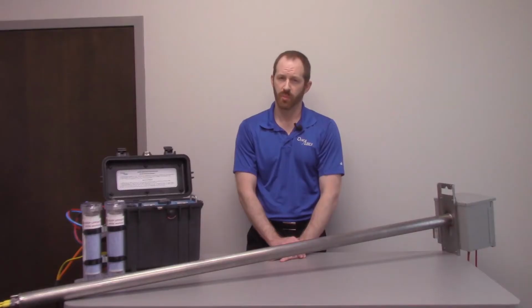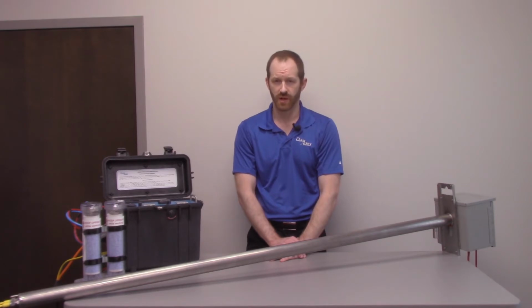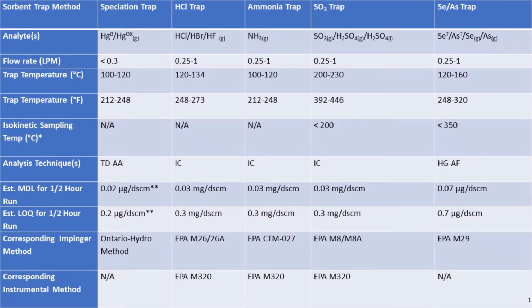It's very easy to operate the OLM30B. I'll walk you through a step-by-step demonstration so you can see for yourself. Before you begin sampling, the first step is to ensure you know all the appropriate sampling parameters for your specific application. Every type of sorbent trap has a unique set of sampling parameters, and the way you sample the traps will most certainly depend on the characteristics of the sample gas, such as temperature and whether there is significant particulate matter in the gas. Our sampling experts will guide you through the specific procedure for your application.